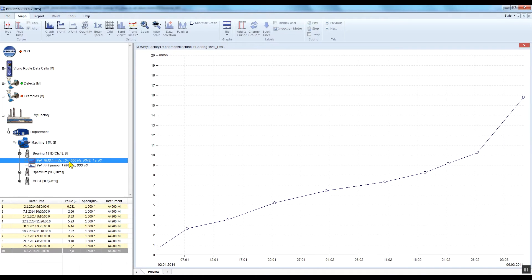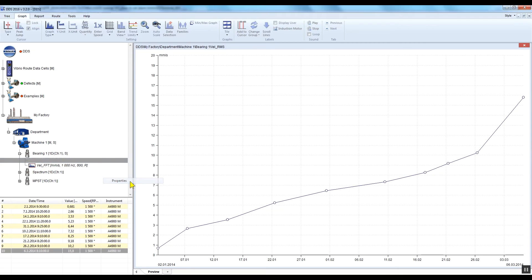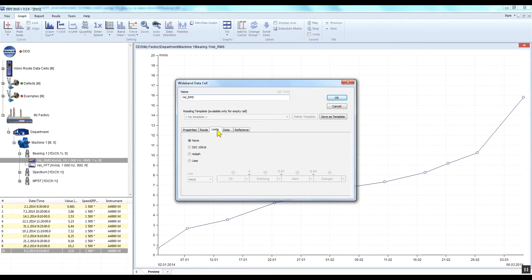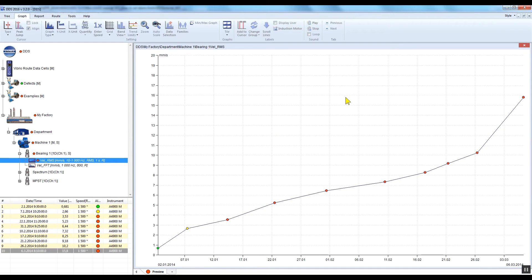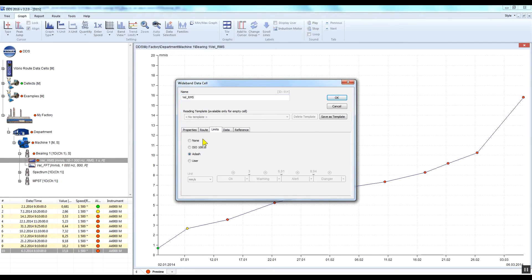To set the Adash alarm limits, right-click on one of the mentioned data cells. Click Properties, go to the Limits tab, select Adash, and confirm by clicking OK. Individual measurements will change their colour according to the applied limits. To switch off limit values, go to Properties again, Limits tab, click None, and confirm by clicking OK.